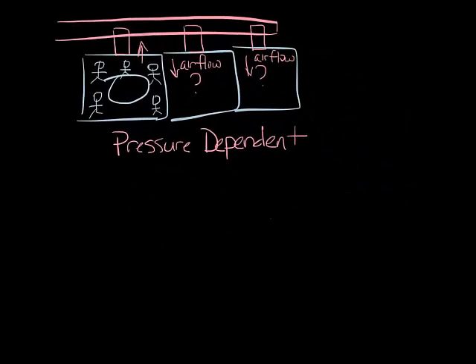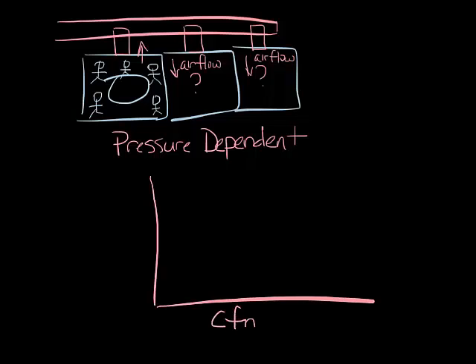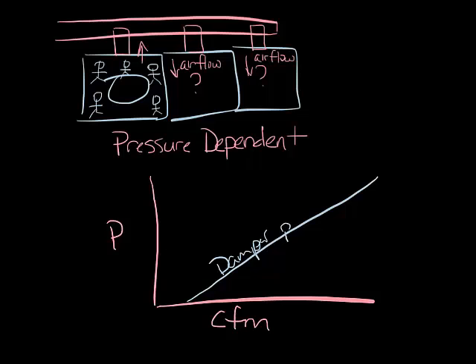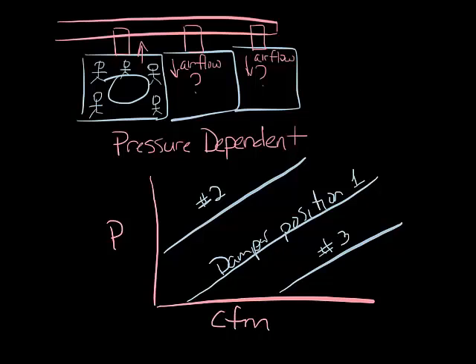If we graph airflow versus pressure in a pressure dependent system, it'll look something like this, where for any specific damper position, as the pressure increases, so does the airflow. So if the damper is in a starting position — position one — the airflow will go up and down if the pressure changes. If you need to change the damper position to let in more air, it'll still float up and down based on pressure changes in the system.